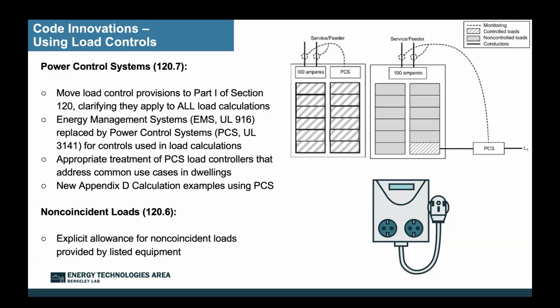We now have a new section addressing power control systems, 120.7. Power control systems are going to replace the idea of energy management systems for this purpose in the electrical code. The main difference is that a power control system will have been evaluated for safely managing power for the purpose of this kind of load calculation, whereas energy management systems are not evaluated for their safety or ability to do that — they're evaluated in other ways, but not in this way. So we've added a lot of content for these PCS systems that reflect common use cases in dwellings.